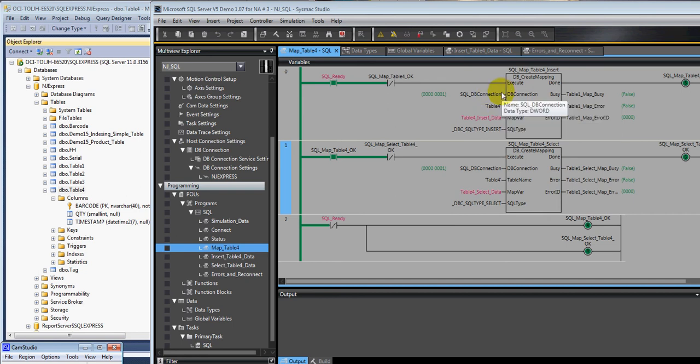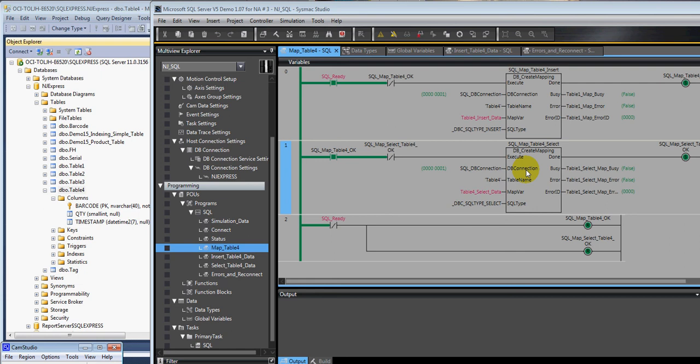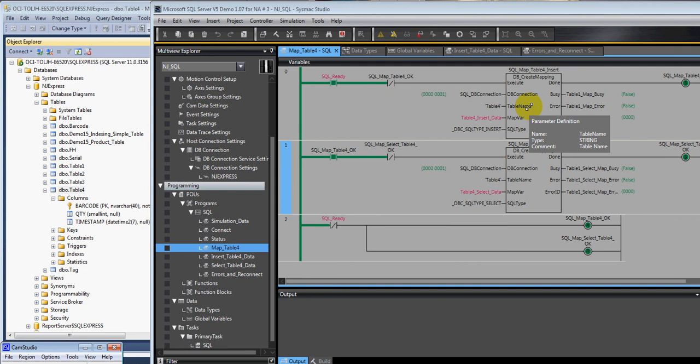So one of the methods I use to keep myself out of trouble is I execute the create mappings one at a time in sequence. And how I do that is I just literally turn on a bit when it's done, and I use that to turn this rung off and drive the next one. And I would do that 10, 20, 30 times, however many mappings I have.